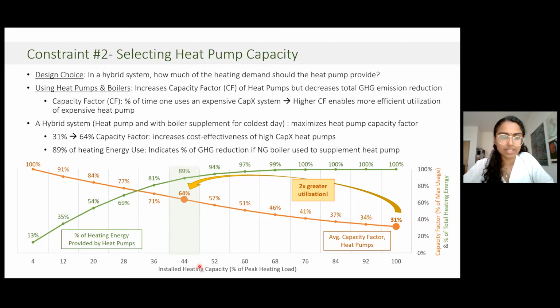And how we're able to achieve this is that we're taking advantage of the fact that most of the hours are spent at temperatures that are greater than 30 degrees Fahrenheit, and each of these temperature bins doesn't require as much heating power as we do in the colder regions. So what we're able to find is that we can size a system where we have heat pumps for temperatures greater than 30 degrees Fahrenheit, and we're able to increase the utilization of that heat pump, as well as achieve a 90% reduction of the carbon emissions from our existing system.